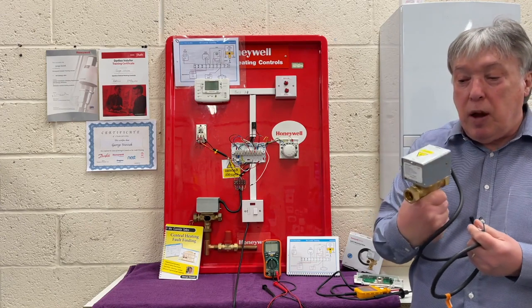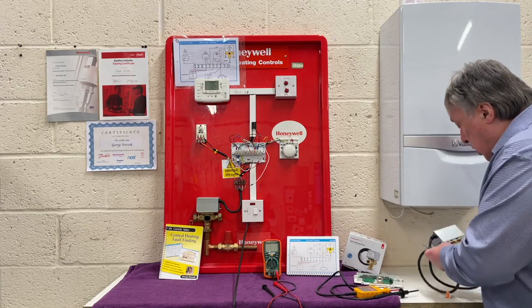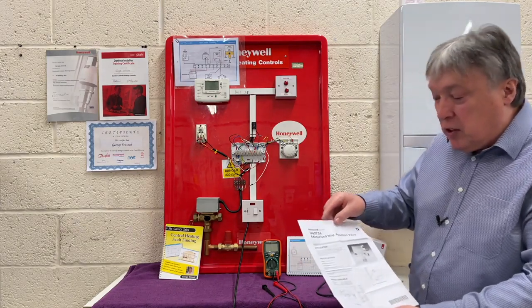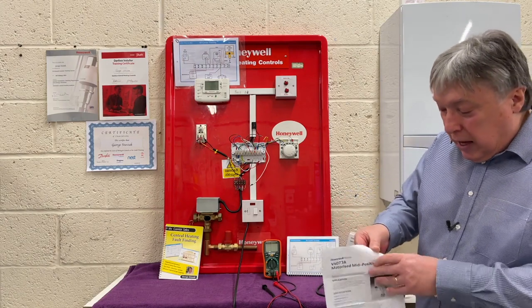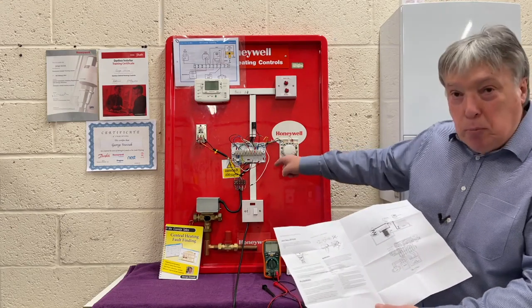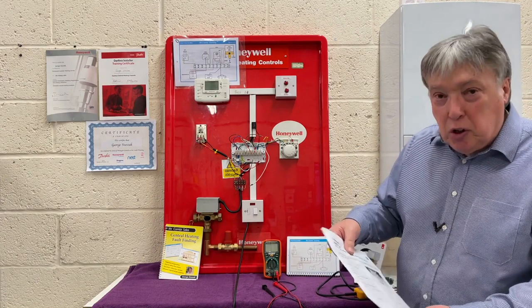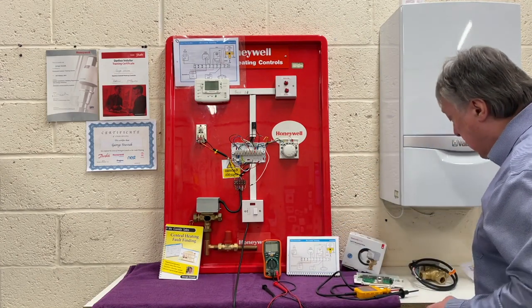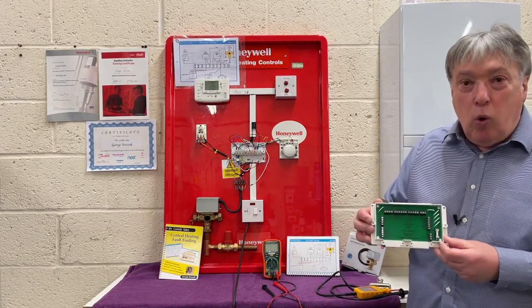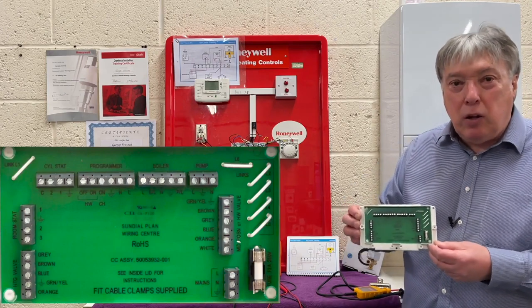Inside you'll also get a leaflet, as always, covering positioning and the way it's wired up to a junction box. Now, as professionals, we don't use junction boxes — we use wiring centres. This is the Honeywell wiring centre for S-plans, Y-plans, and a couple of others. But we're interested in Y-plan in this video.